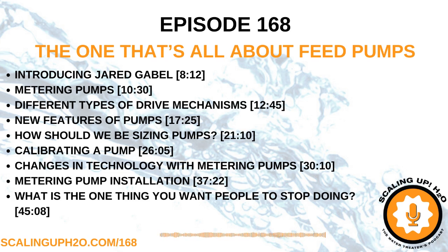So anytime you get into the pump, and it's doing something completely strange electronically, that's when I would normally go directly to the manufacturer. If you try to start opening up the body of those pumps, you can risk things like voiding the warranties, and it takes away any control of our ability to identify the problem later and then give credit back to you as a customer. So don't be opening the brains of the pump, I guess, if you're not a brain surgeon. There you go. That's a great way to put it.